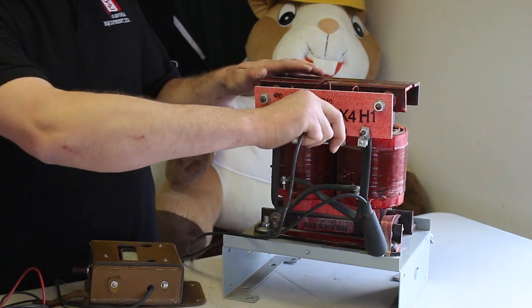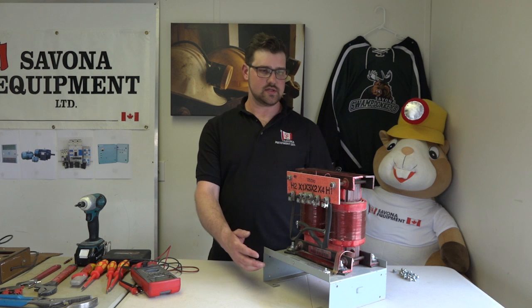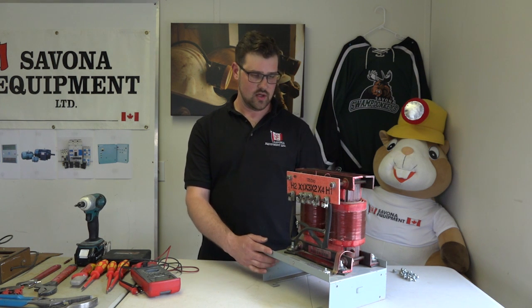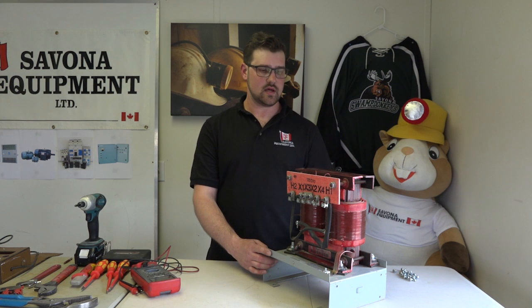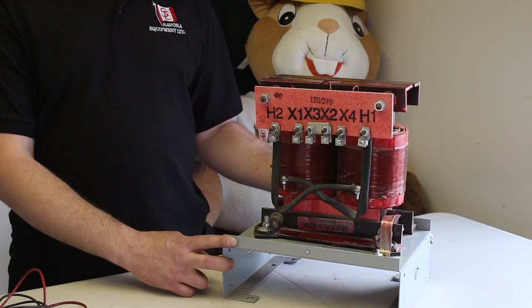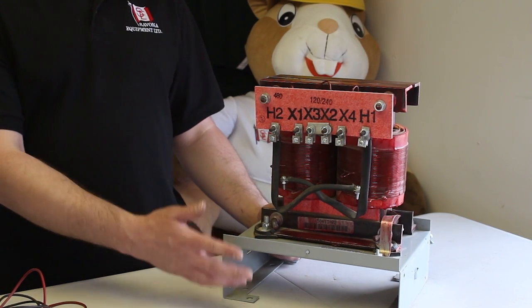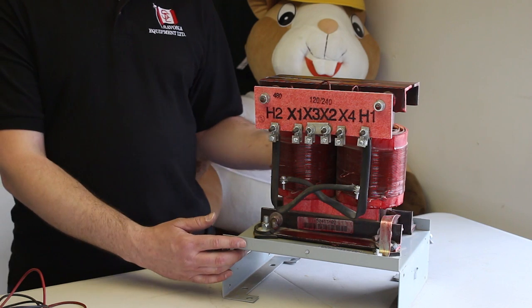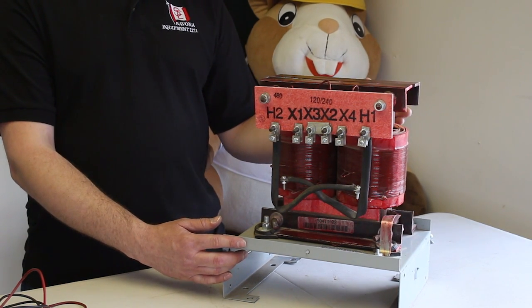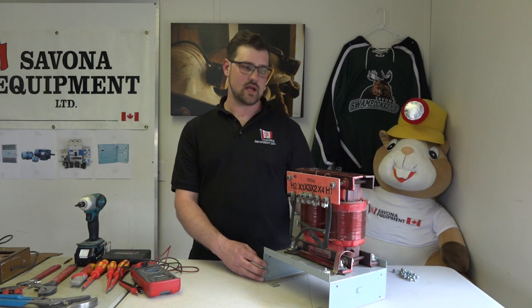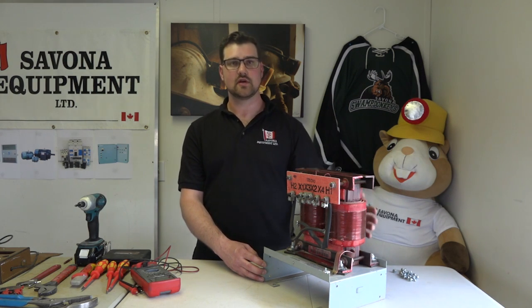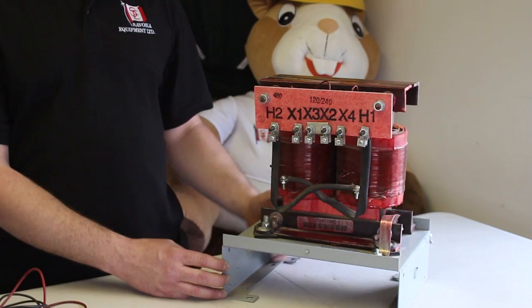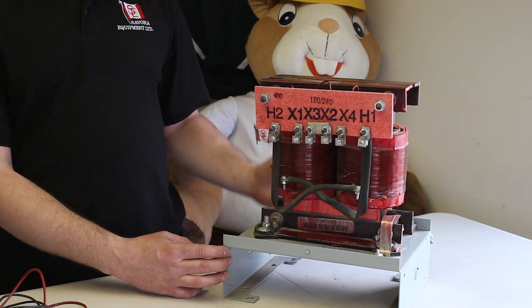That's good there. Okay, so now that we've tested the transformer, we know that it's a good transformer and this is something that we can sell. We'll list it on our website. There you can find, we have dry type transformers, oil filled transformers, high voltage transformers, pad mount transformers, and this is something that Savona Equipment actually sells a lot of. The reason being, transformers are a piece of equipment that has no moving parts, and most of the time these pieces of equipment are protected with either a breaker or fusible disconnects. So if there is a piece of equipment that fails, that usually doesn't get back to the transformer, so that's a reason why they don't become ruined.